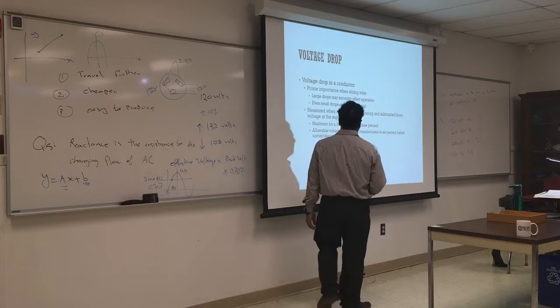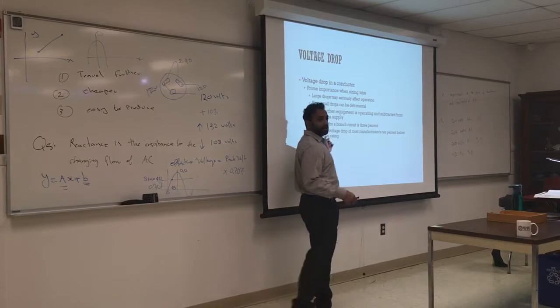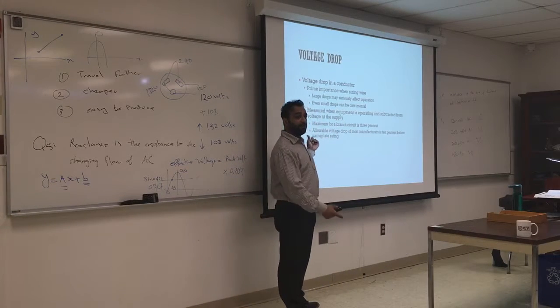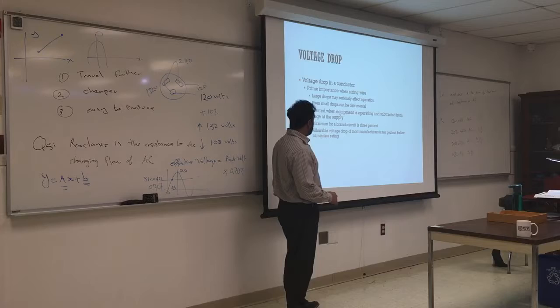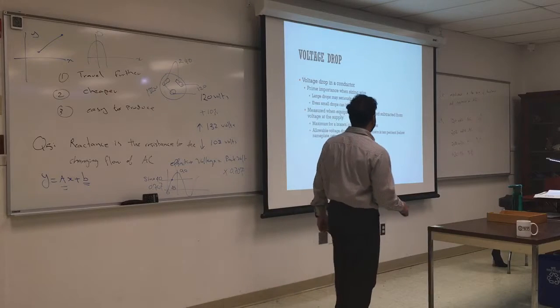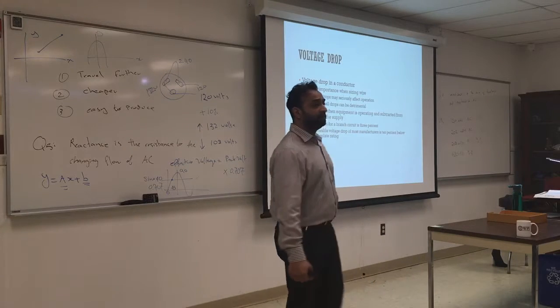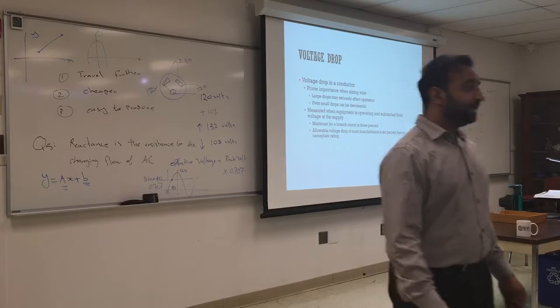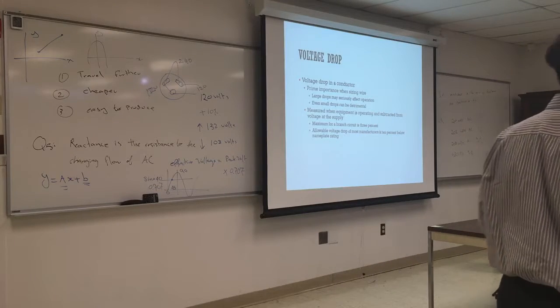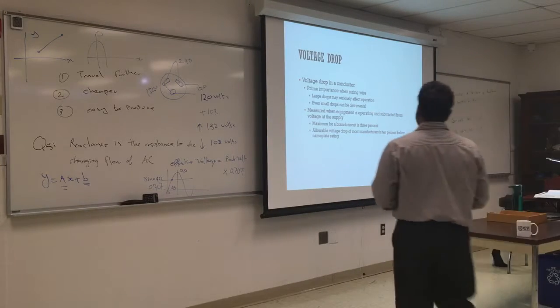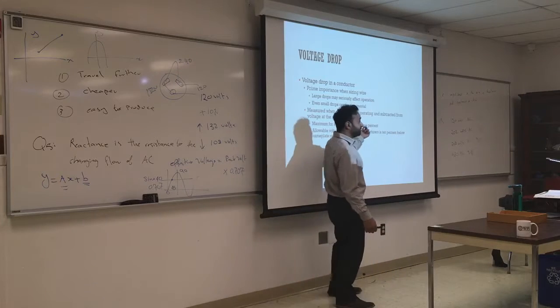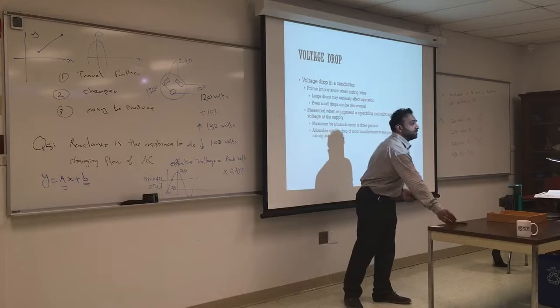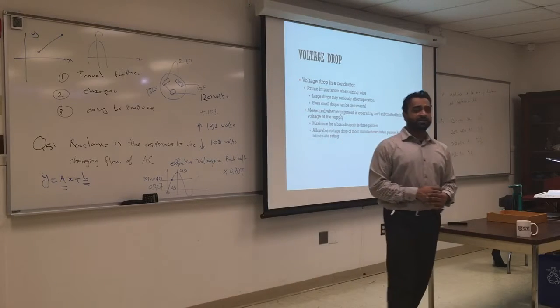So the maximum for a branch circuit is 3% plus or minus. What is the branch? It's from the main power to the equipment. Allowable voltage drop for most manufacturers is 10% below the nameplate rating. So what is the nameplate? It's what's printed on the equipment as the voltage required for that. Remember this number for a branch is a 3% drop. That's from the main line to the branch. What is considered a branch?